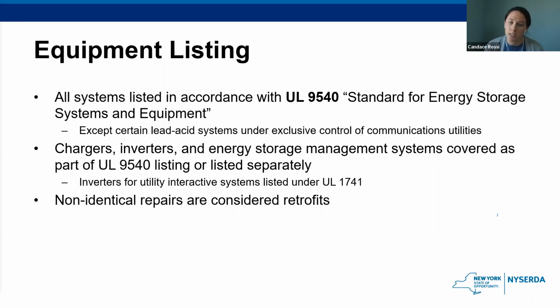And then to further safeguard against hazards, systems must also be listed in accordance with UL 9540, which is the standard for energy storage systems and equipment. Chargers, inverters, energy storage system management systems, if not already covered as part of UL 9540, must be listed separately. And then if it's a utility interactive system, the inverters must be listed under UL 1741 and labeled for that use. And if systems are repaired with anything other than identical parts, it will be considered a retrofit and subject to a permit application, and have many of the same requirements as a new system. So this is just making sure that all the equipment that is used is UL listed and safe and ready to be used.